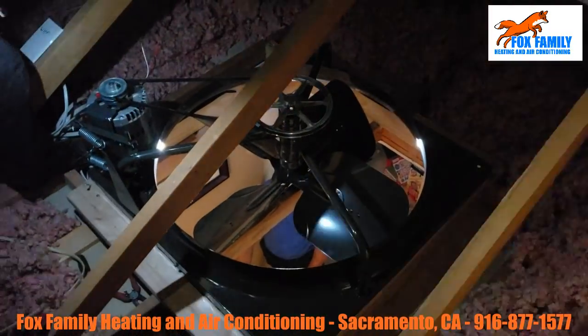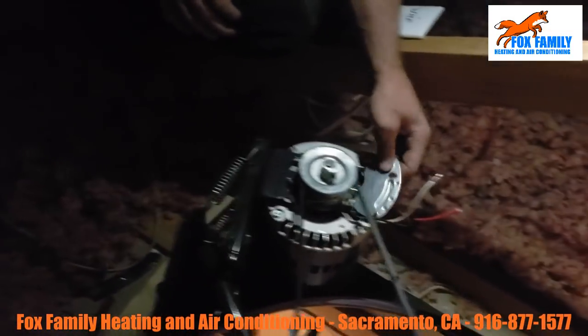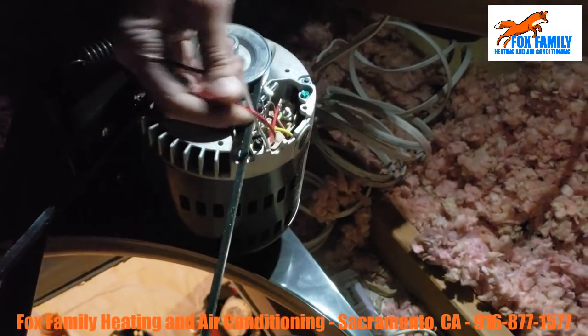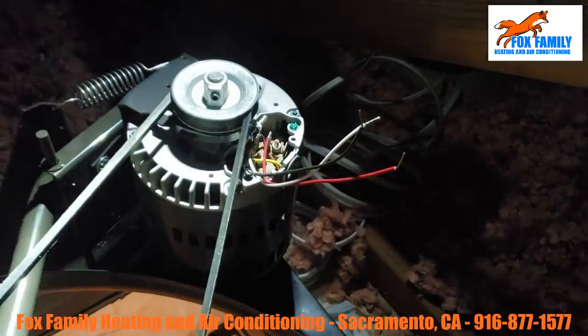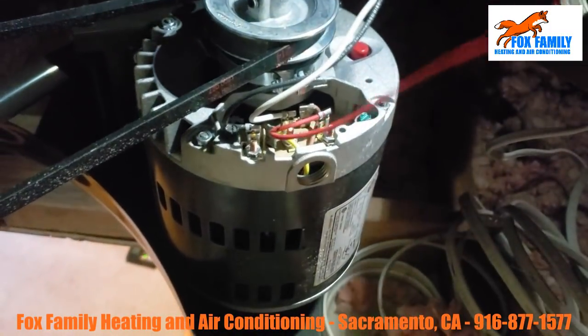That's the only two screws holding on that initial frame, huh? You could just take your high speed, low speed, neutral wires and just hang them out and wire nut them out here. But in California, you can't do that. That's not up to code. So we're going to use a 3/8 Romex connector, run the Romex into here, then wire nut everything in and smash it down into that.